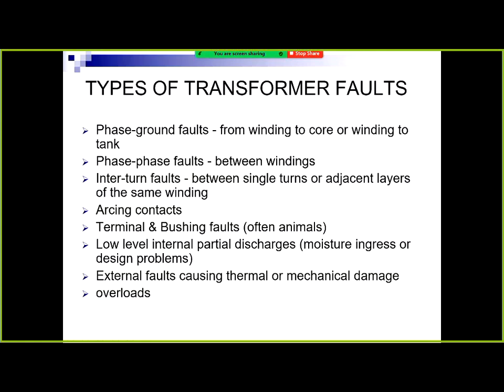I'd say the most common are your terminal and bushing faults. They're the ones that I've seen the most. External transformer faults, probably not very common because we rate our transformers to a fault current rating and we monitor that. Years ago, that other one was a smaller 66 to 33 or 22 kV transformer, so they may not have monitored as well in a distribution board which had 50 people and only 10, 15 engineers, so they didn't monitor those things as well.